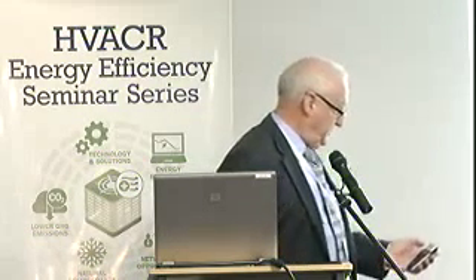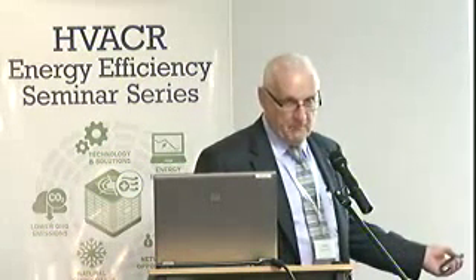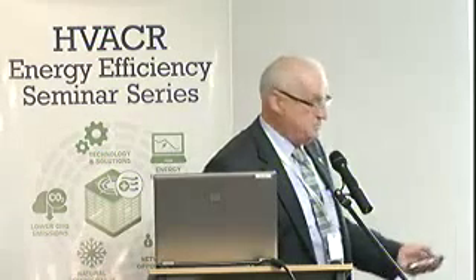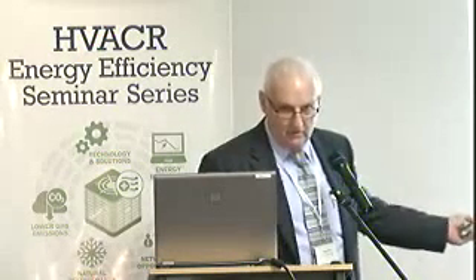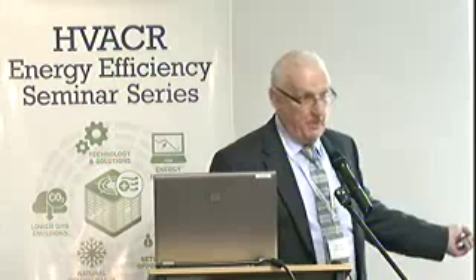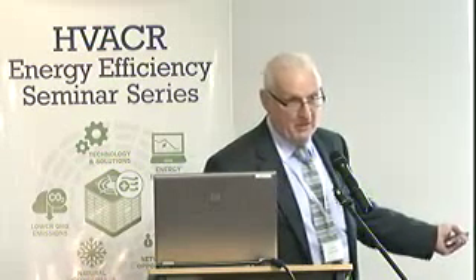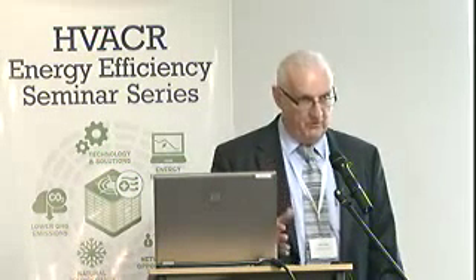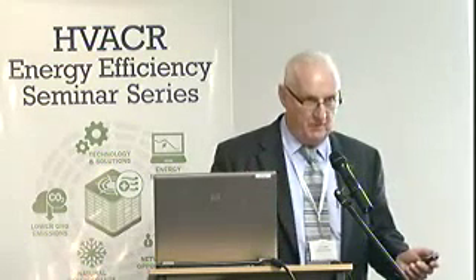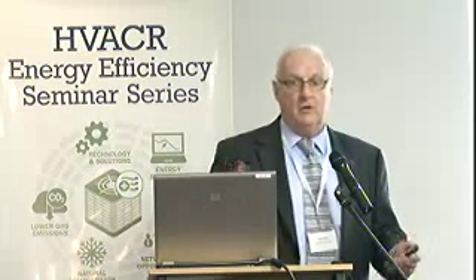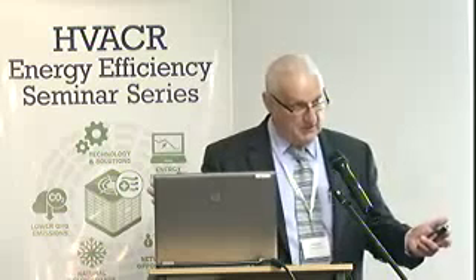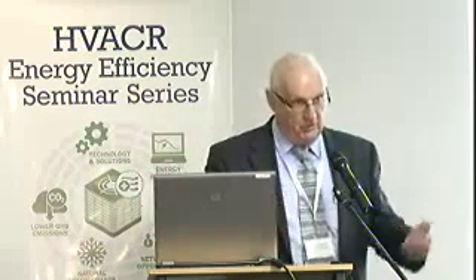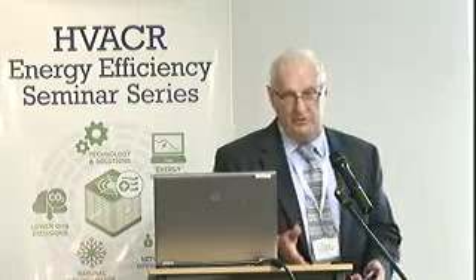So here I've got circled a Bitzer refrigeration compressor motor nameplate, just because most of you probably never look at the nameplate on an electric motor, and I didn't before I got into the VPO game either. It's amazing how many motors are actually designed for 380 volts as their optimum performance level. There are still 415 volt motors nameplated out there, although often that will be on the outside of a packaged unit, and you open the door and have a look at the compressors, and guess what? It'll be 380 volts. It's surprising how often you find that.